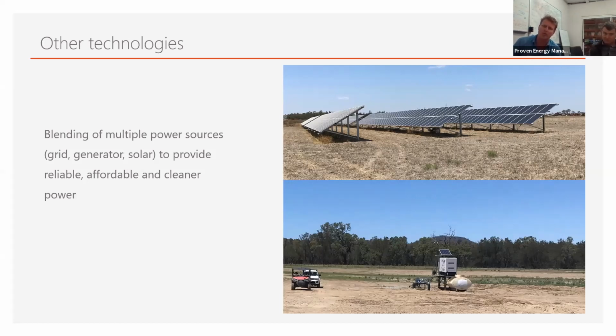And just run solely on the solar. And in the afternoon, as the sun starts going down, start the diesel generator back up, and gradually, as the sun drops down, the diesel generator takes over the full pumping load. So this is quite an efficient way of using the DC input and an existing diesel generator, with a special variable speed drive. And there's no network connection there.